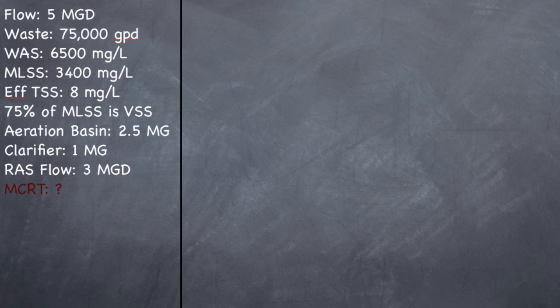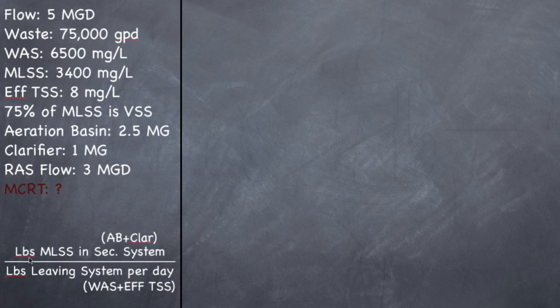So the formula for MCRT is pounds of mixed liquor suspended solids. It's not MLVSS, it's MLSS in your secondary system, which is your aeration basin plus your clarifier, divided by pounds leaving the system per day, your waste activated sludge plus your effluent TSS. So first we need to figure out how many pounds of MLSS is in the secondary system.